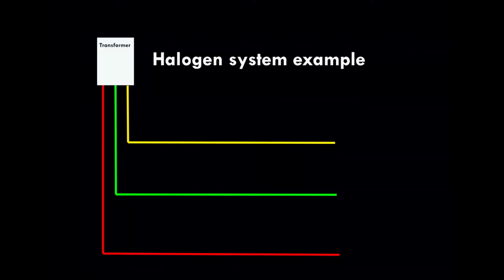To know what size of transformer to purchase for your project, you must start out with a basic lighting design. Now this design should spell out what you want to light, how many fixtures will be required, and what the wattage of the bulbs you plan to use in each fixture is. As an example, we're going to look at figuring the size of a transformer needed for a halogen system. The three colored wires you see represent 3 home runs that run from our transformer to the fixtures.